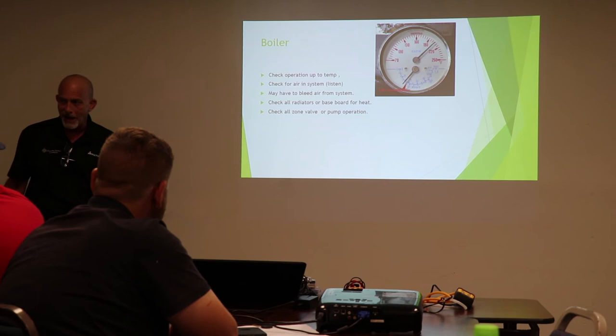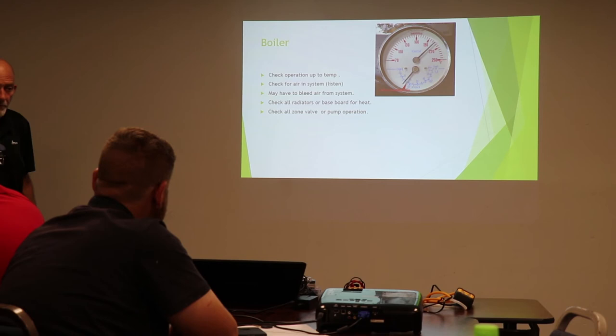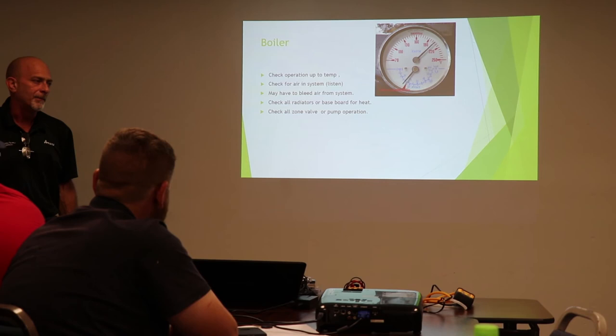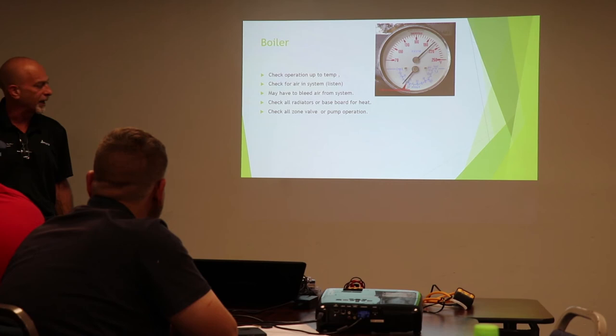Check our operation, bring our boiler up to operating temperature, and make sure that our aquastat shuts our boiler off at the proper temperature. Typically nowadays, it can be about 180. On some of your radiators, you can run it a little bit hotter, but if you got baseboard, it's gonna be about 180. 12 to 15 PSI operating pressure.